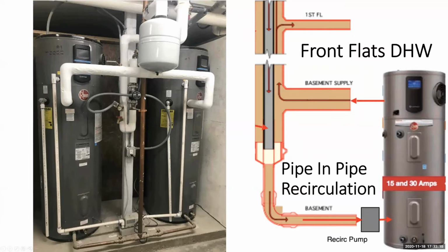And there's 4 sets of these throughout the basement, or maybe it's 6, I forget. But each one of these 2 80-gallon tanks together is handling 4 residences above it. And that's a common way that I design apartments, is to share 1 tank among 2 households, like a big 80-gallon tank stored at 140 Fahrenheit with the heat pump only mode, so we don't use any of this 15 or 30 amps electric resistance that it's saying there in red on that tank. That's all electric resistance there. It only needs about 7 amps or so when it's running in heat pump only mode. So it's also very power efficient.